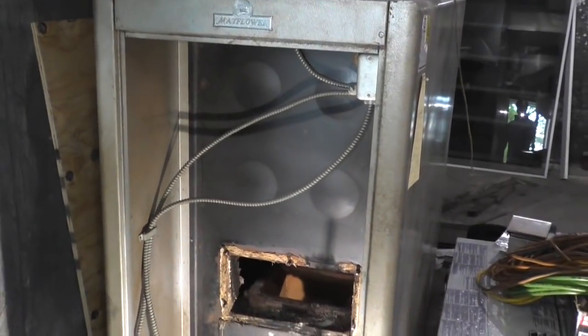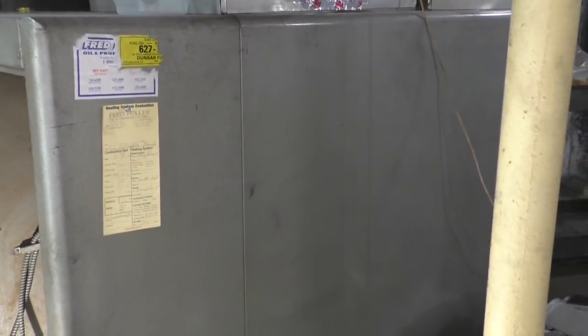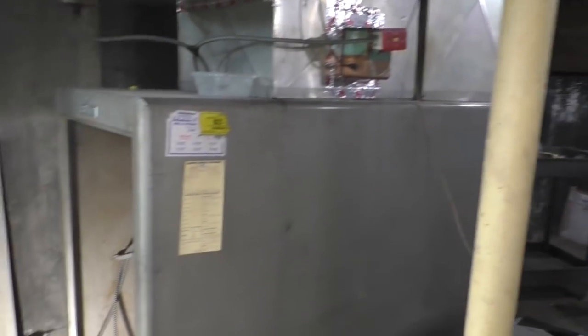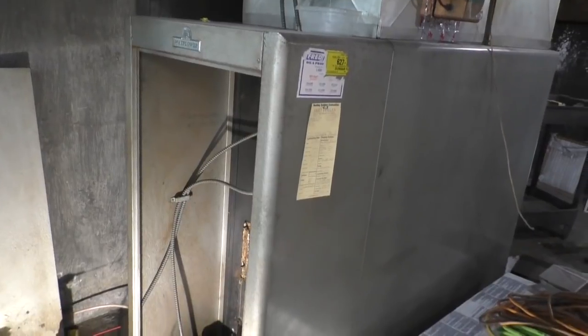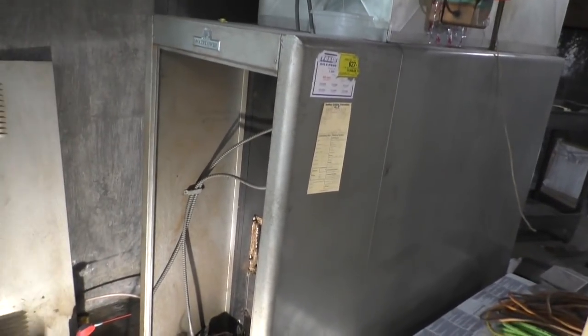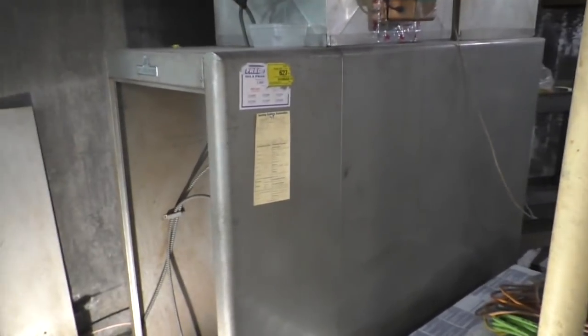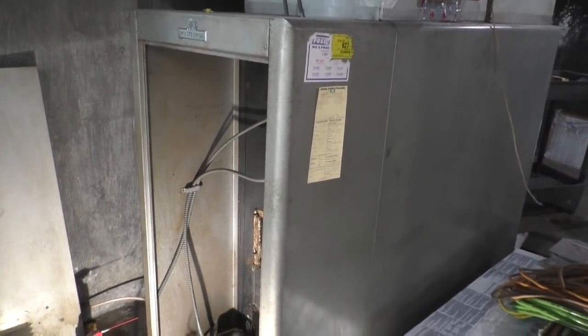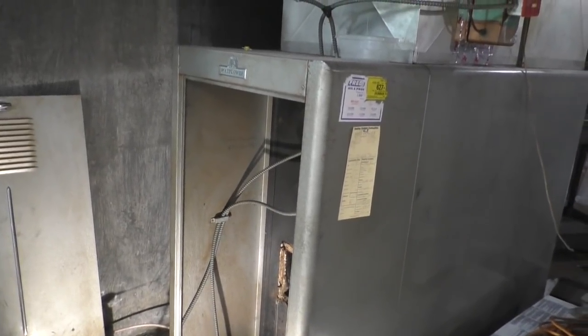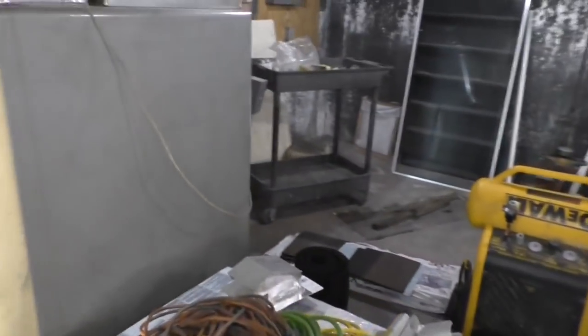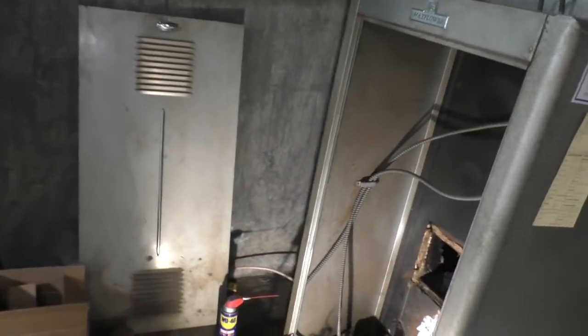We're gonna go ahead and have this unit replaced. It has done well. I will say, you would have never known there was a problem at all. Well, let me rephrase that - yes, you would know, because it was constantly cutting off on high temp, which is a big problem. I knew there was something going on, and I'm like, well, maybe it just needs a new nozzle. No, that heat exchanger is blocked, and you can see there's corrosion there, and it's only a matter of time before that corrosion eats through that probably quarter-inch thick deck plating, which is what they would have used back then. Of course, I'm exaggerating.